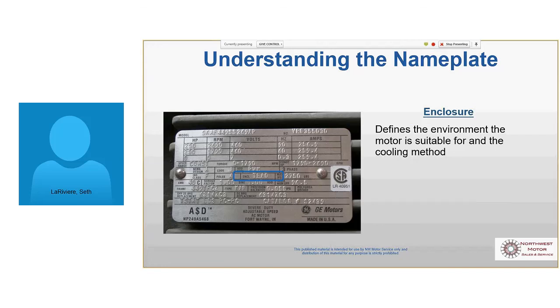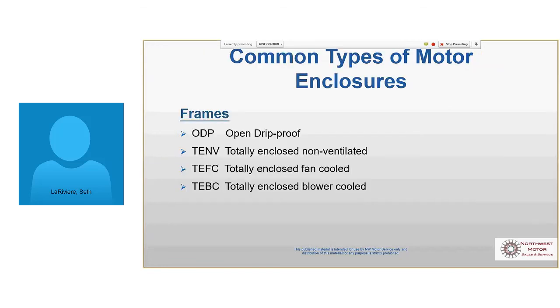These are the real common enclosures. Open drip proof, I'm sure you guys see a lot of those. Those are open, as the name implies, free exchange of inside and outside air. So not good in a hazardous location, explosion proof, not good in a dusty or wet environment. But if it's clean indoors, they cool themselves better than a TEFC motor, so they run cooler, so they last longer. So I like open drip proofs in clean, really clean indoor applications.